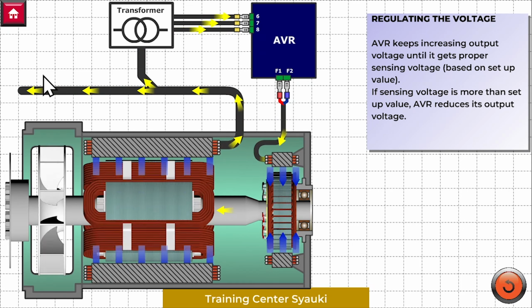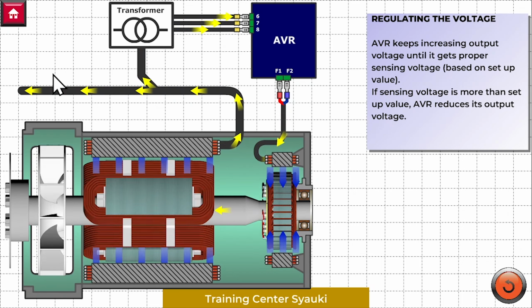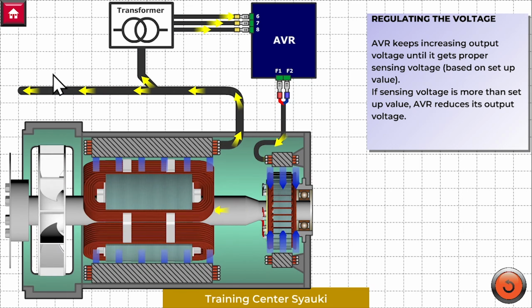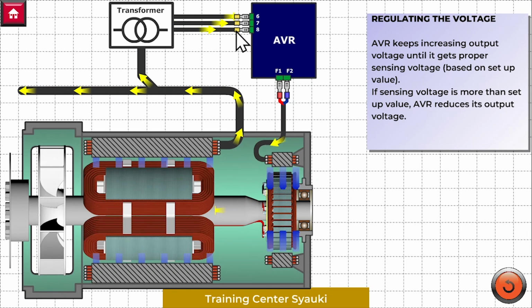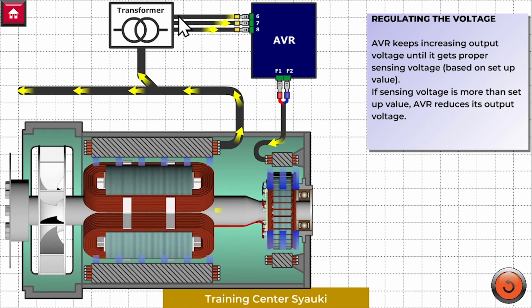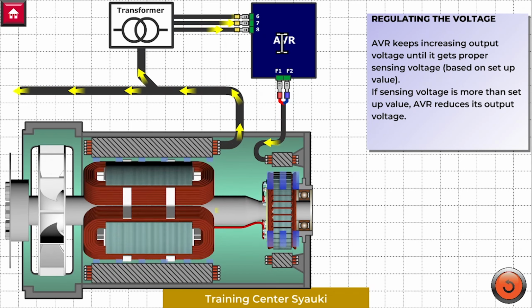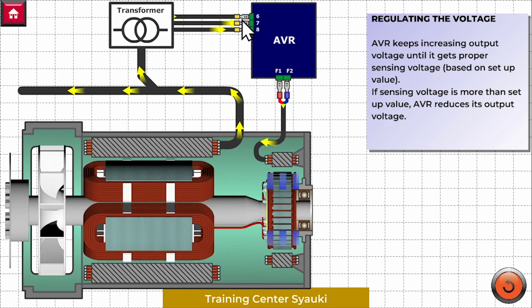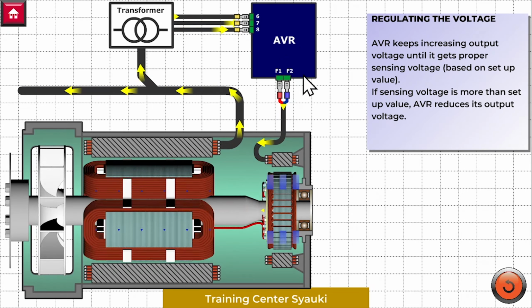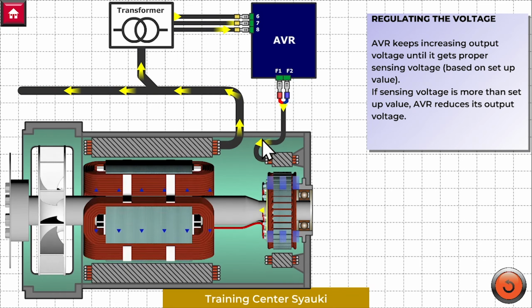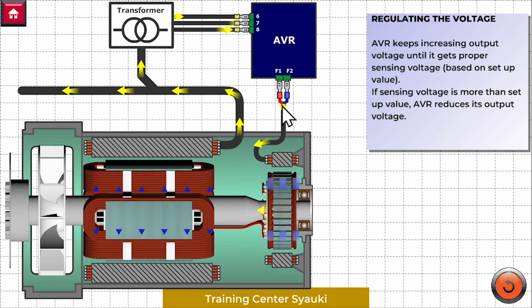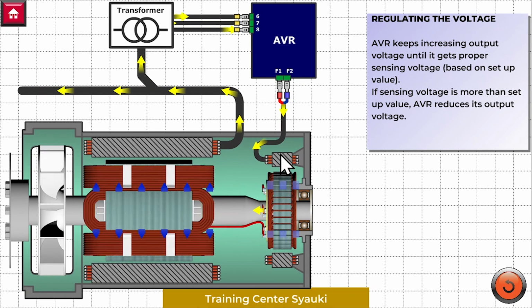If we give load to this generator, the voltage will be reduced. So the AVR will read from the transformer and compare with the setup value. If the sensing is lower than the setup value, the AVR will increase the output to the exciter stator.